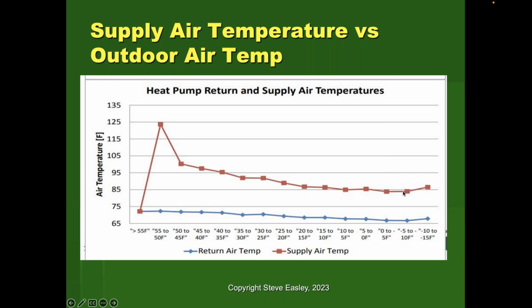One of the things I've noticed in communities where they've basically outlawed new natural gas hookups, and people have replaced their gas furnaces with heat pumps, and pay close attention to this, they install the new heat pump and the people say, wait a minute, it feels like cold air is coming out of the register. The reason it feels that way is that traditional heat pumps have somewhat lower discharge temperatures. Newer models, of course, can have much higher discharge temperatures.